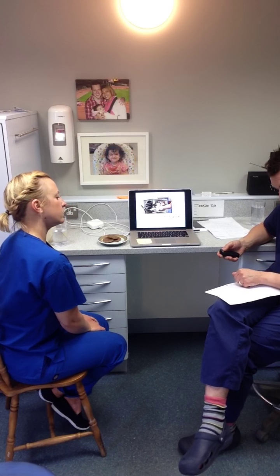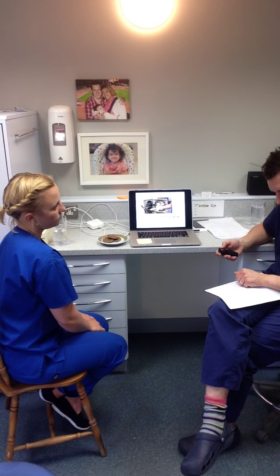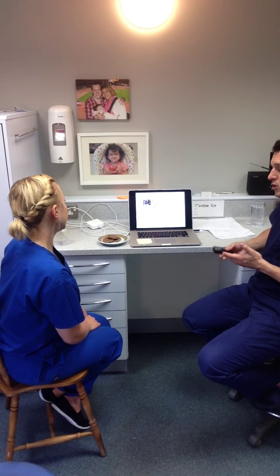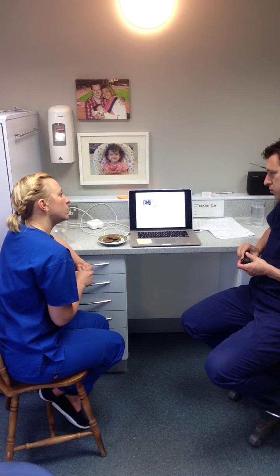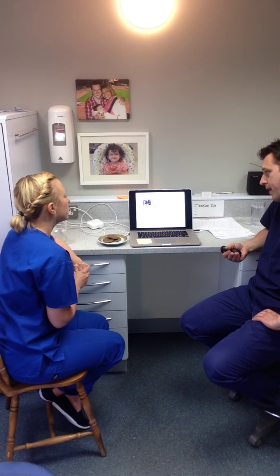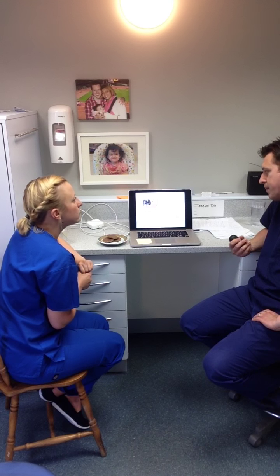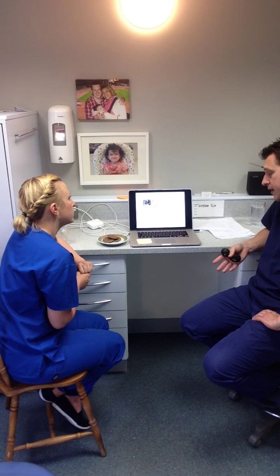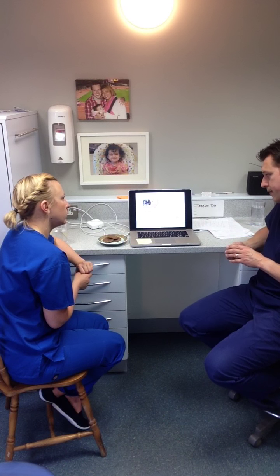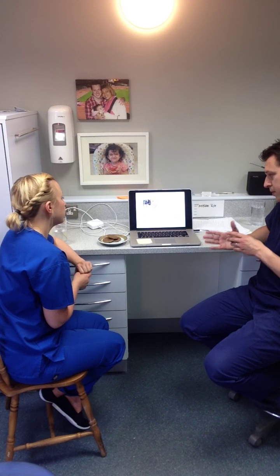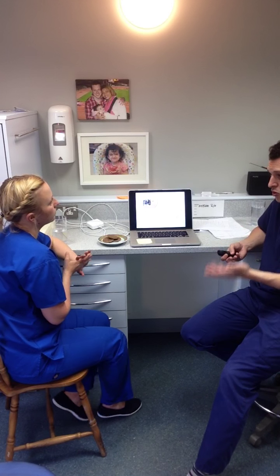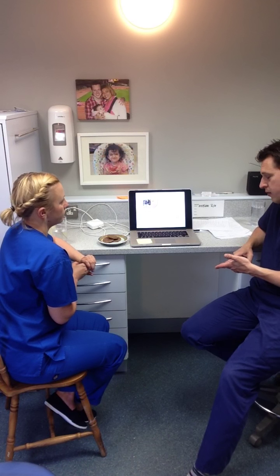So, on to sterilisation. Sterilisation is usually performed by autoclaves. It's saturated steam put under pressure, and that achieves sterilisation. It takes place after cleaning and disinfection, so you've got to get all that out of the way before you put the instruments in the autoclave. And the big thing is it's validated. This is the part of our decontamination process that's validated. We've got a data printer, so we get a print-off to say that the autoclave has maintained the right temperature for the right time.